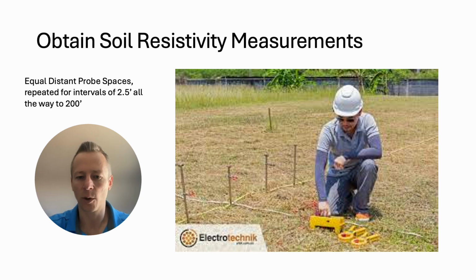I'll have to double check the exact equation for how deep you're theoretically measuring based off your probe spacing, but it is directly tied to the probe spacing. So the further out you get your probe spacing for that A value on the previous slide, effectively the deeper into the soil you're taking into account. So what's typically done is you drive 4 probes like that, you take your measurement, then you pull up the probes and you go spread them out to a higher A value, a higher spacing. And we typically go all the way from the first measurement of 2.5, 5-foot spacing, 10-foot spacing, 20-foot, 30-foot, all the way out to 200 feet if you have that much room.